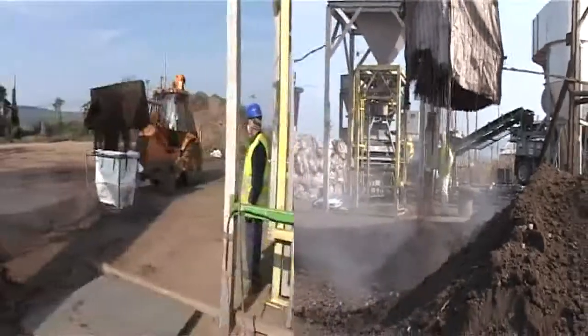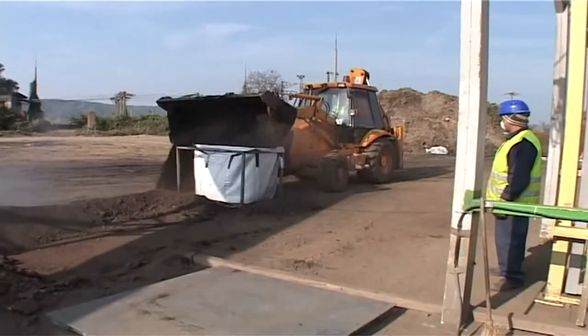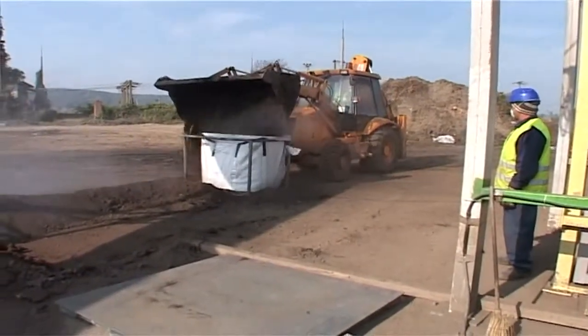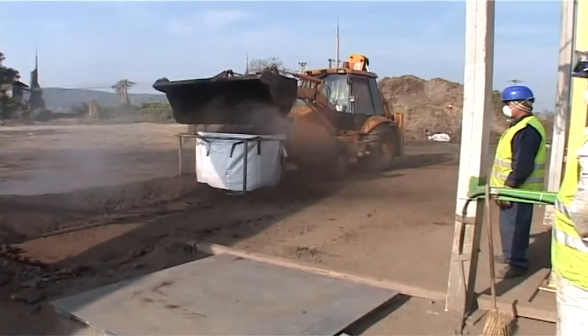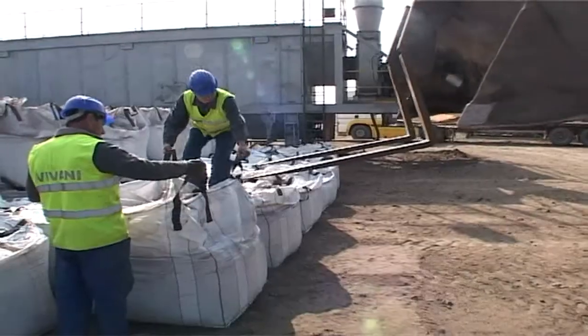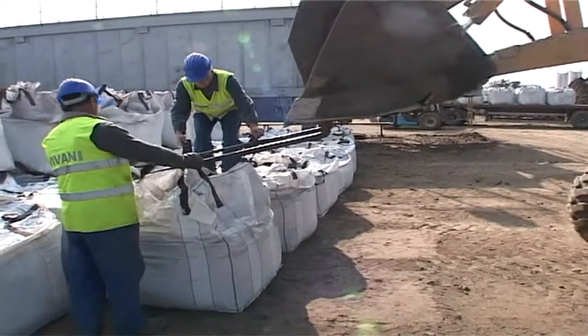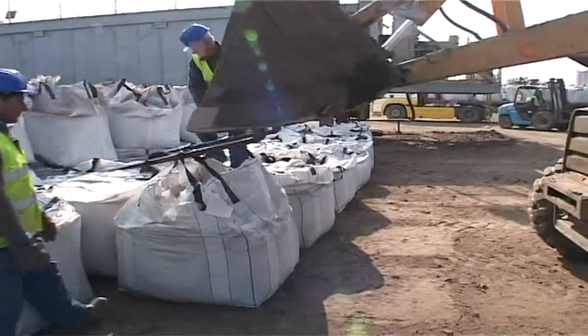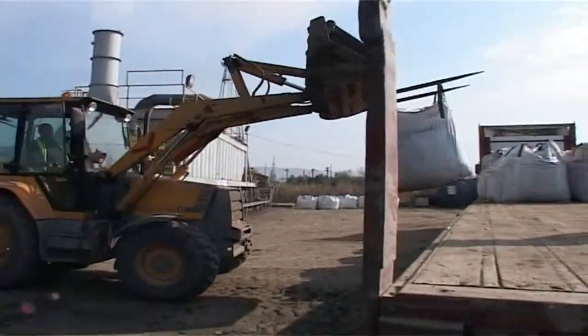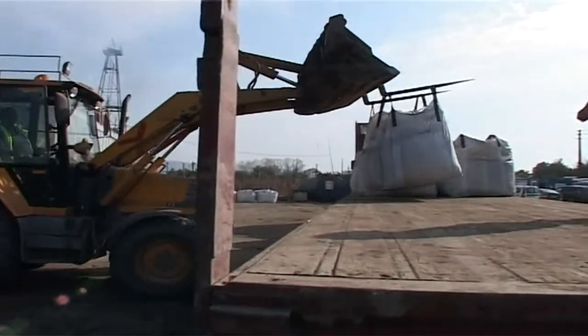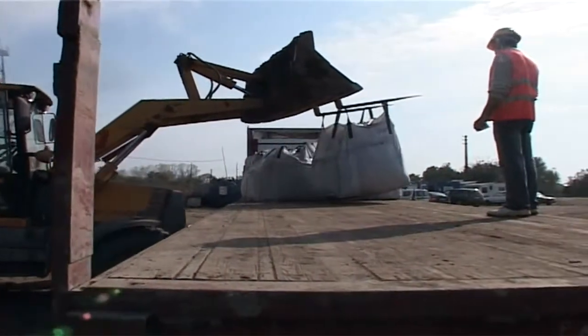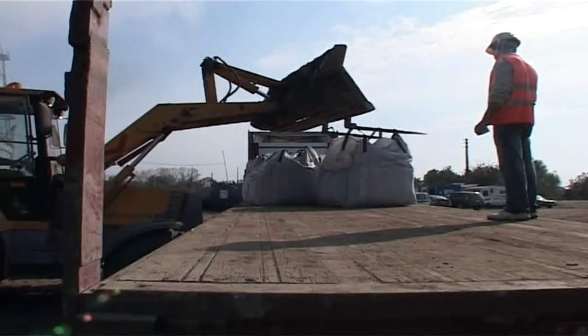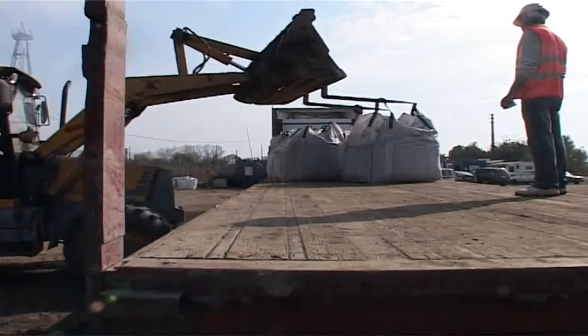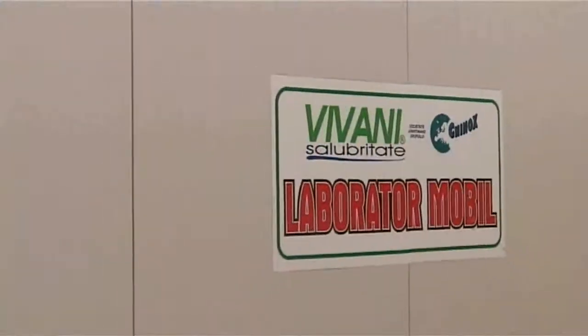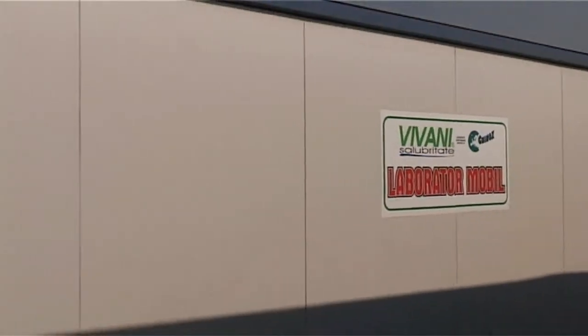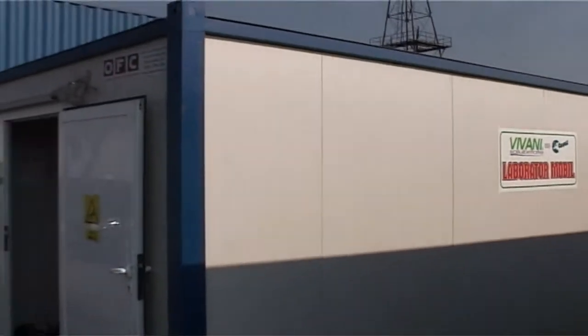The TPH water is removed from the centrifugal through a pipe in a transfer container, which will discharge it into the water network. The sludge is removed from the centrifugal at the lower end and carried to the temporary platform by a conveyor worm. The sludge leaving the centrifugal has the following features: humidity between 7 and 9% and TPH content less than 5%. From the temporary platform, the sludge is then carried by a loading machine into the feed bin of the desorption plant.